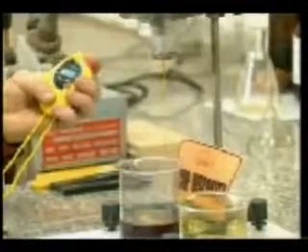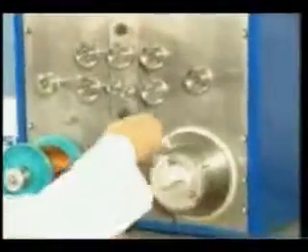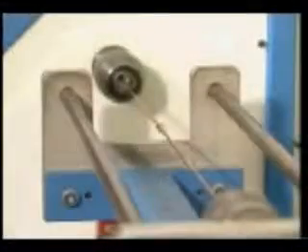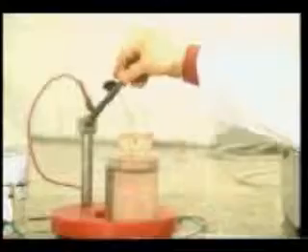Passing by various online tests and ending by a full sampling final product testing procedures that include physical tests such as measuring the wire diameter before and after insulation, electrical tests such as continuity test, resistivity test, and tangent delta test, thermal tests such as cut-through test, chemical tests such as solderability test, and organic solvents resistance test, mechanical tests such as elongation test, spring back test, and peel test, and measurement of thin layer thickness for thin copper wire.